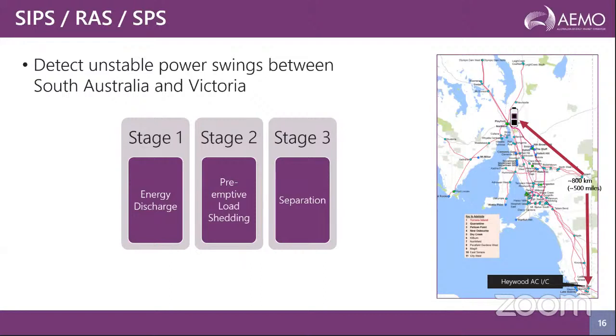The scheme would detect the potential loss of synchronism between South Australia and Victoria or other NEM regions. If it detects the potential loss of synchronism, it will send a signal to battery, and the battery has reserved megawatt. So battery would discharge its megawatt into the grid and thereby try to relieve the load on the interconnector and potentially defer the loss of synchronism between South Australia and other regions.